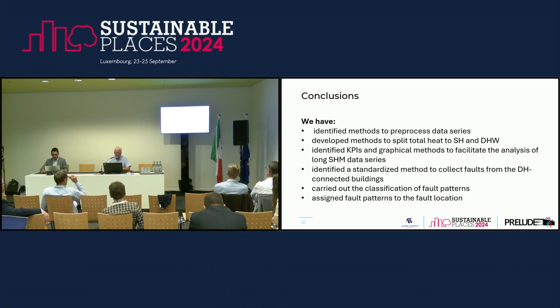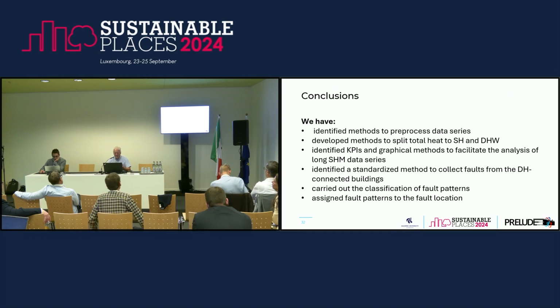In conclusion, we have developed a method to pre-process the data series so we get more accurate data as a basis for our analysis. We developed a method to split total heat into two parts: space heating and domestic hot water. We also identified indicators and graphical methods to facilitate analysis of the time series, and standardized methods to collect faults. When we got the first fault reports, every company had their own way of making these reports, so we developed a common methodology for the district heating company so that all contractors used the same fault report, ensuring consistent information — without that, it's very difficult to develop methodologies.